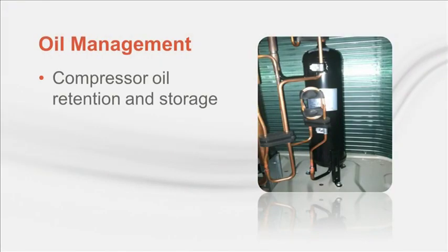Looking at all this refrigerant pipe might have you asking, what about oil return? This is a legitimate concern and an obvious question. Well, let's take a look at how VRF manufacturers handle this. First, the compressors must be designed with adequate internal storage capacity, so they have large sumps. Next, the addition of an oil separator helps capture most of the oil that is pumped out of the compressor and is injected back to the compressor.